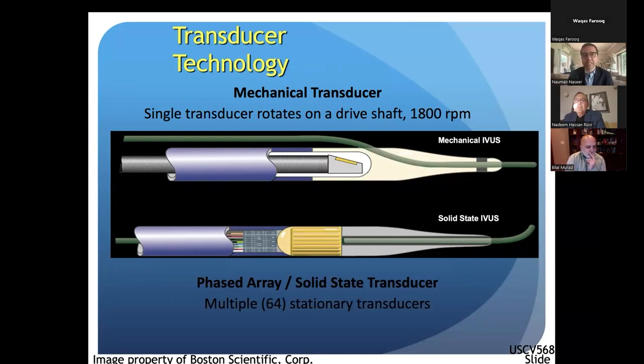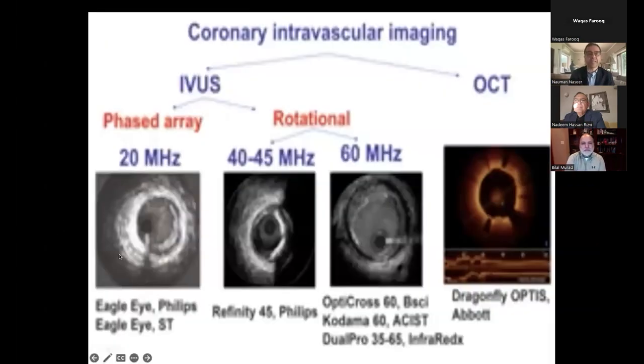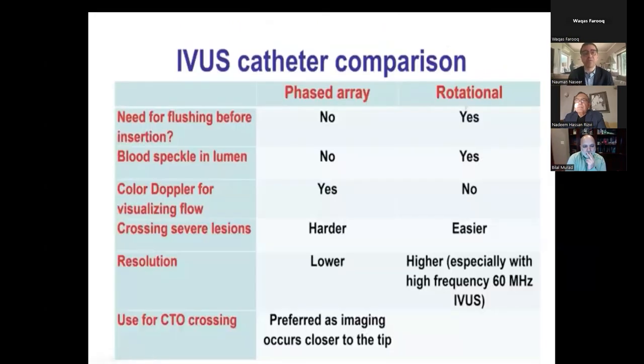The Boston Scientific is a single transducer which rotates like a lighthouse effect on a drive shaft at 1800 RPMs. And the phased array solid state transducer is multiple, 64 stationary transducers, which emit the ultrasound waves. Now this is phased array. It does not have as high a frequency as the rotational catheters. So Eagle Eye, which we have over here, is 20 megahertz typically, and you can get on rotational catheters 40, 45, and with some of the other rotational catheters up to 60 megahertz frequency, with a better resolution. And this is the OCT image with even better resolution over here.